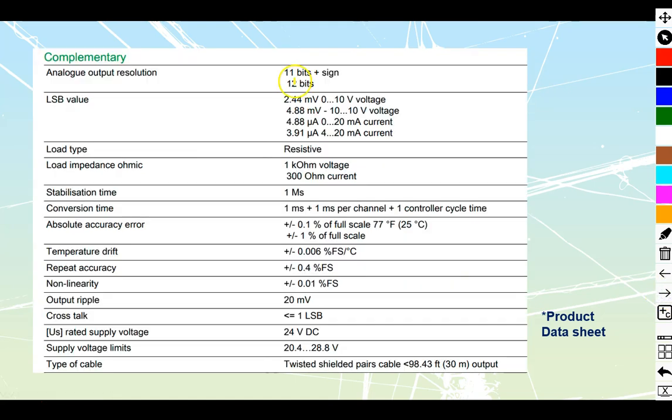Looking a little bit further in, we find information about the accuracy or resolution. It's going to be 12 bits of accuracy - 11 bits plus a sign, plus or minus. It's going to be a little bit more coarse than what we can get on the input. Inputs range up to 16 bits. These are going to be slightly coarser because we're applying that output.